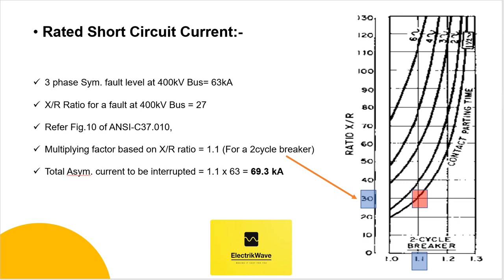Referring to figure 10 of ANSI C37.010, three-phase and line-to-ground fault multiplying factors include the effects of DC decrement only. The multiplying factor based on X by R ratio is 1.1 for a two-cycle breaker, as shown in the figure. So the total asymmetrical current to be interrupted would be 1.1 multiplied by 63, which equals 69.3 kA.